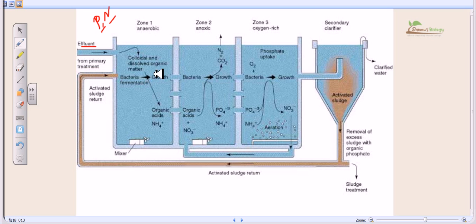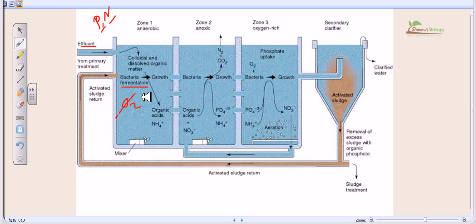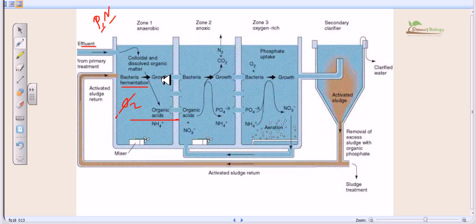Bacteria are added to the water and they start to grow using fermentation — a technique to produce energy and utilize nutrients under anaerobic conditions where there is no oxygen. The bacteria use fermentation to turn those nutrients into alcohol or organic acids, such as acetic acid. So they take up nutrients from the wastewater and convert them into organic acids and a small amount of ammonia or ammonium salts.